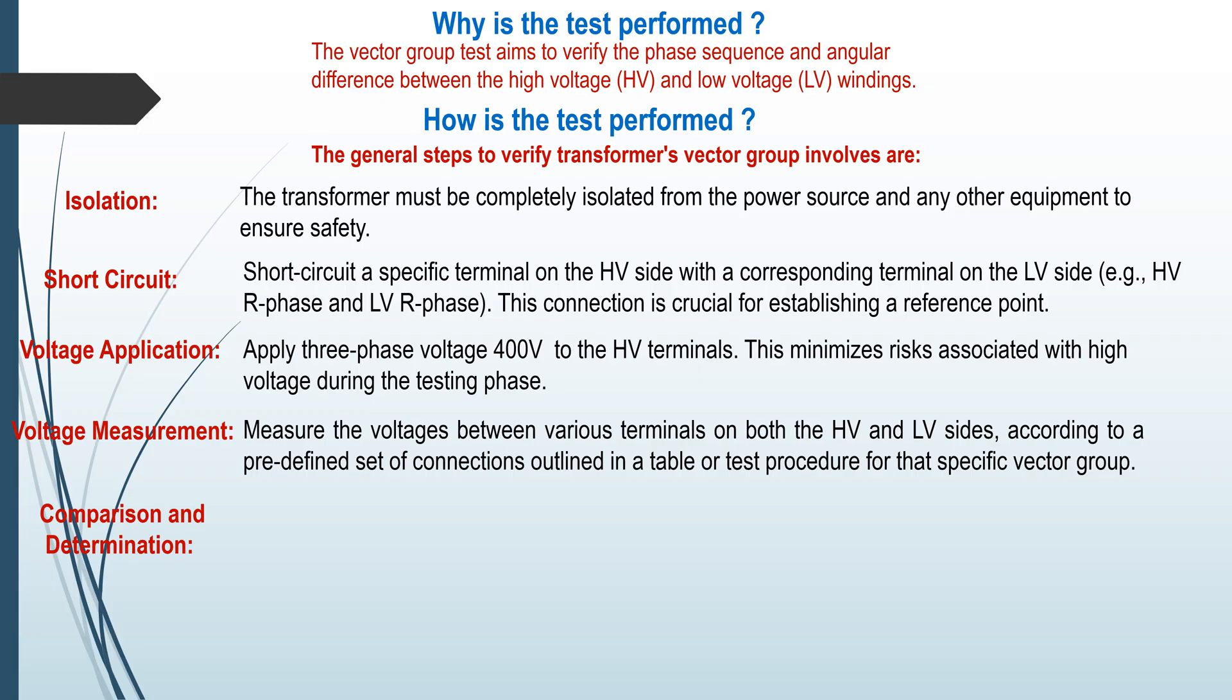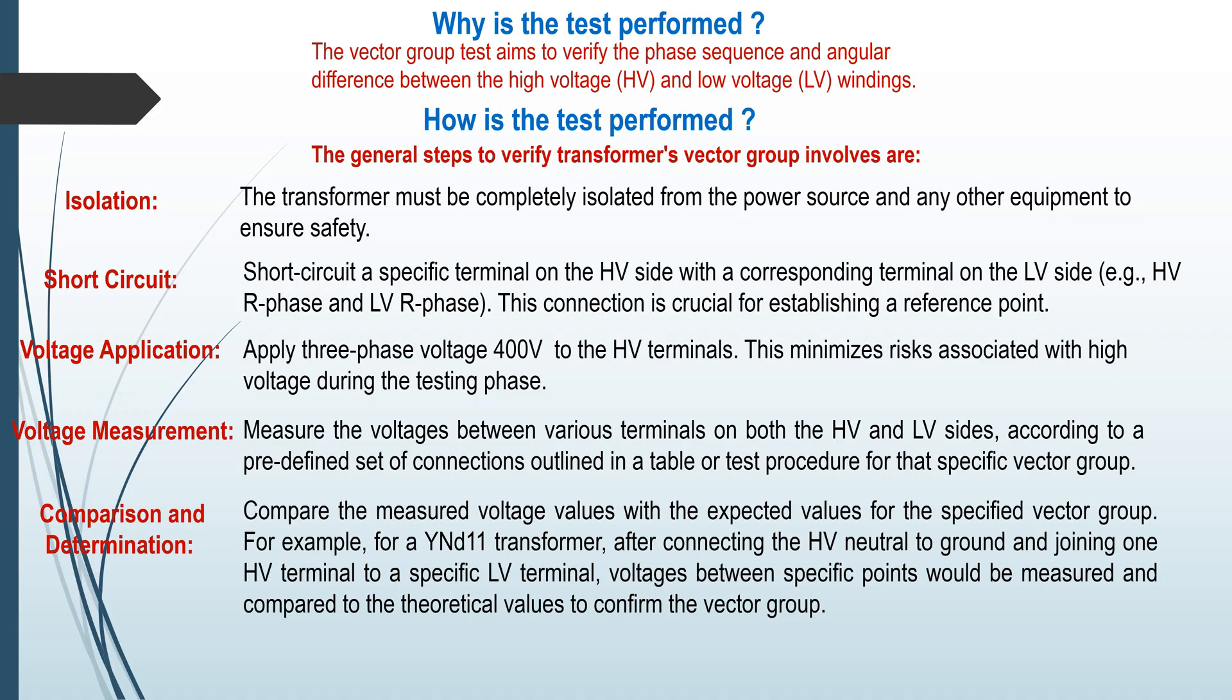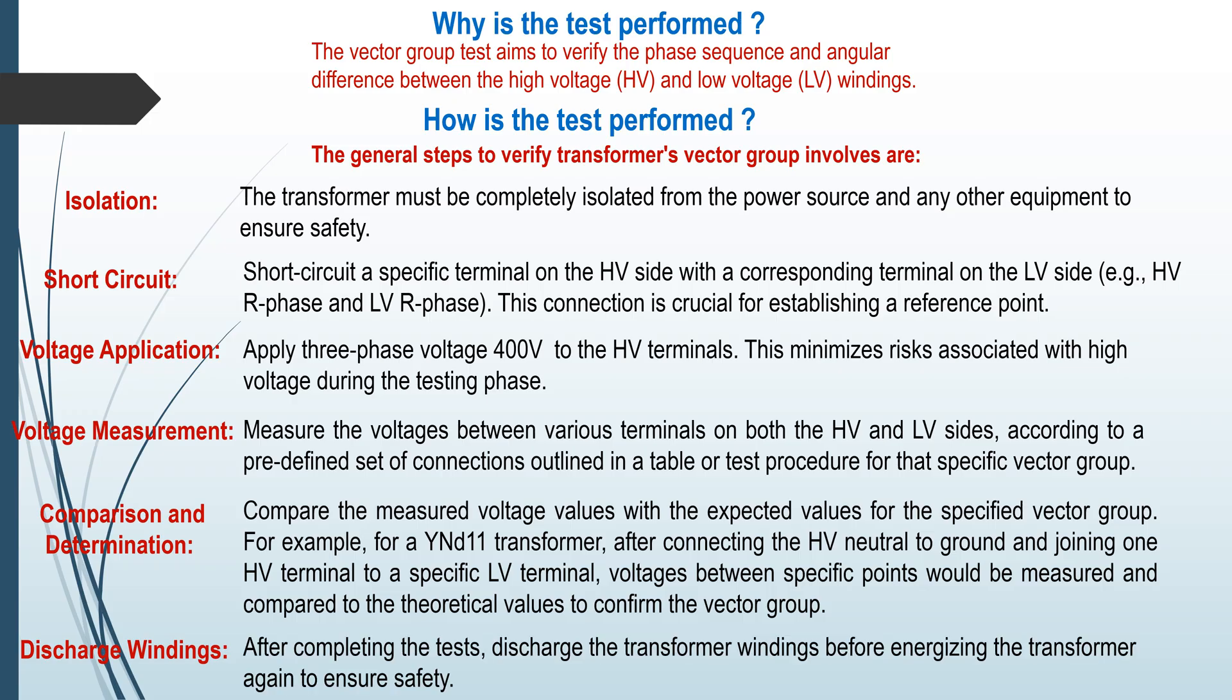Comparison and determination: Compare the measured voltage values with the expected values for the specified vector group. For example, for a YNd11 transformer, after connecting the HV neutral to ground and joining one HV terminal to a specific LV terminal, voltages between specific points would be measured and compared to the theoretical values to confirm the vector group. Discharge windings: After completing the test, discharge transformer winding before energizing the transformer again to ensure safety.